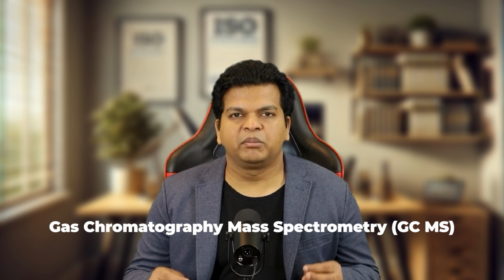Next, let us discuss the analytical techniques for chemical characterization. The success of chemical characterization relies heavily on the analytical techniques used to identify and quantify chemical substances. ISO 10993-18 provides guidance on how to perform chemical characterization, including the selection of extraction conditions and analytical methods. Here are some of the most commonly used techniques. Number one is gas chromatography mass spectrometry (GC-MS). This technique is ideal for detecting volatile and semi-volatile organic compounds. For example, GC-MS can identify residual solvents or low molecular weight additives in polymers.